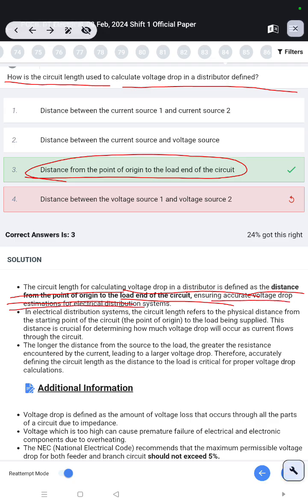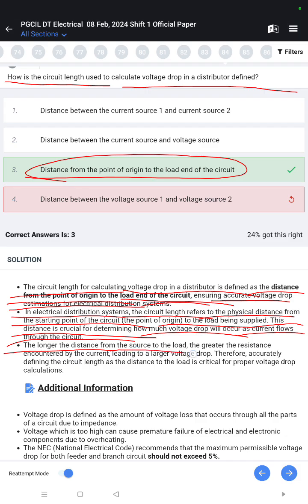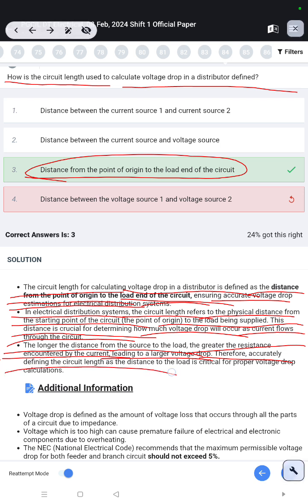In electrical distribution systems, the circuit length refers to the physical distance from the starting point of the circuit, the point of origin, to the load being supplied. This distance is crucial for determining how much voltage drop will occur as current flows through the circuit. The longer the distance from the source to the load, the greater the resistance encountered by the current, leading to a larger voltage drop. Therefore, accurately defining the circuit length as the distance to the load is critical for proper voltage drop calculation.